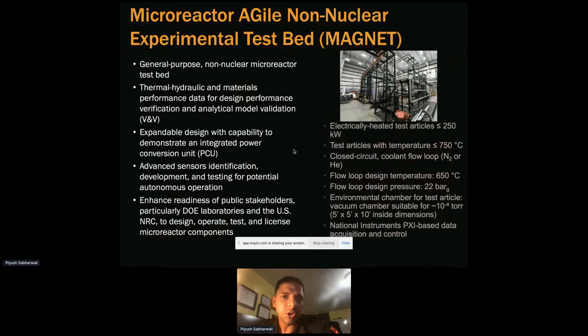MAGNET serves as a general-purpose, non-nuclear test bed to ensure we can do thermal hydraulic and material testing to support V&V needs. The flow loop is designed to 650 degrees Celsius, pressure of 22 bar, and we can achieve a vacuum of 10⁻⁴ torr. We're using PXI-based data acquisition and control from National Instruments for our DAQ system. Data gathered here would enhance readiness of public stakeholders, support other DOE programs, and provide information for NRC to support licensing activities for micro reactors.